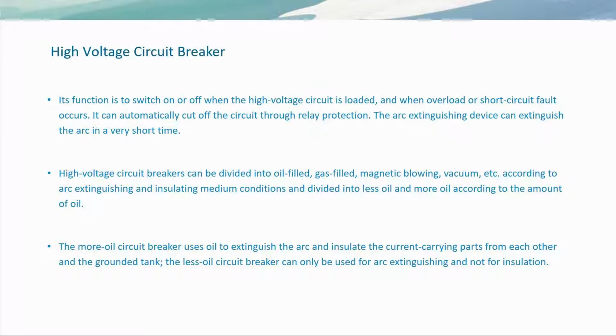Circuit breaker is an important device in high-voltage switchgear. Its function is to switch on or off when the high-voltage circuit is loaded, and when overload or short-circuit fault occurs, it can automatically cut off the circuit through relay protection. The arc extinguishing device can extinguish the arc in a very short time.